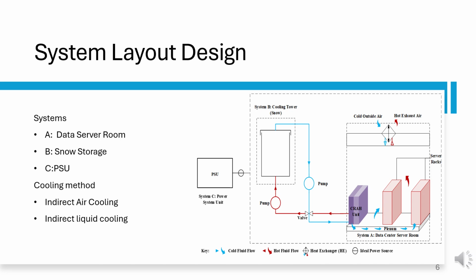And this is directly related to the humidity of a system, because we would not need advanced or complex systems to control the humidity. For the indirect air cooling, a heat exchanger is used to transfer heat from the hot aisle of the server room to the cold air outside without actually mixing them, also for humidity reasons. The layout used for the server room is the hot aisle containment system, and this physically isolates the hot air from mixing in with the cool air, and this basically increases the cooling efficiency of the system.